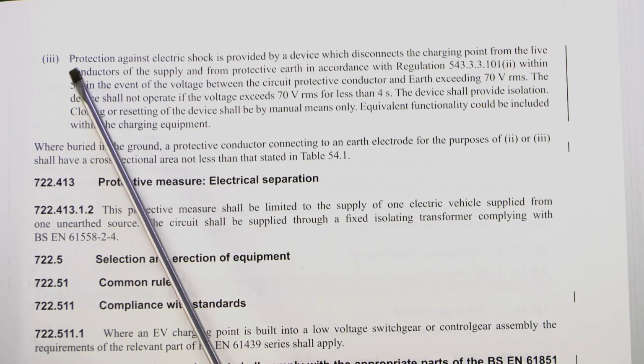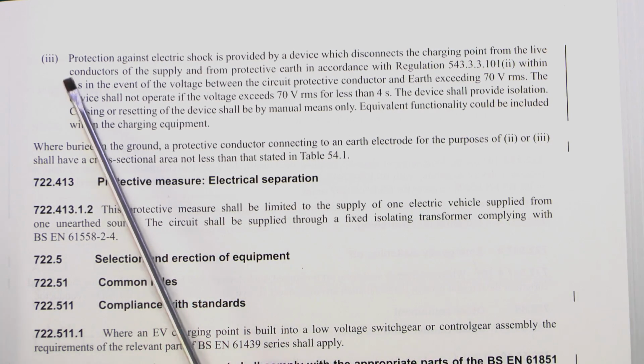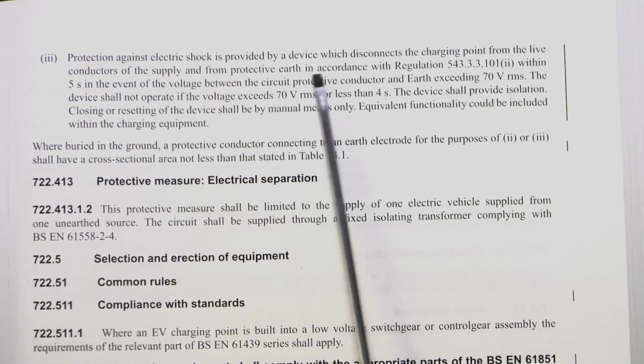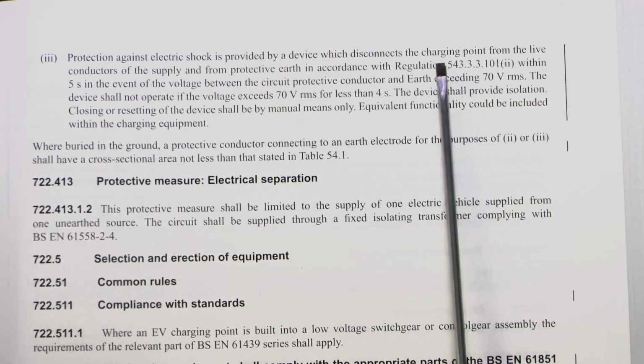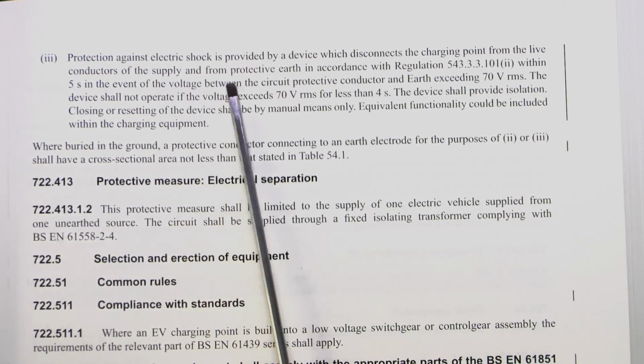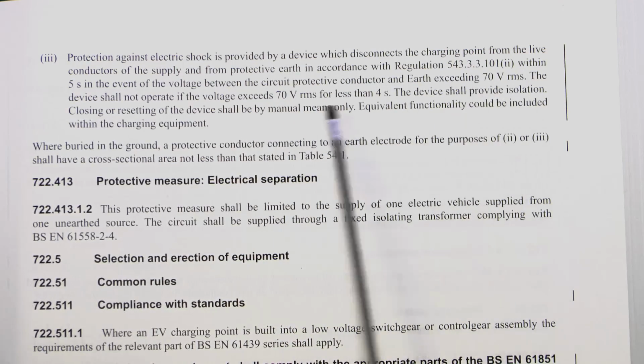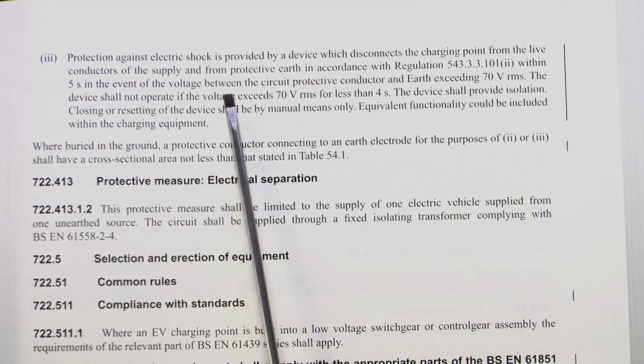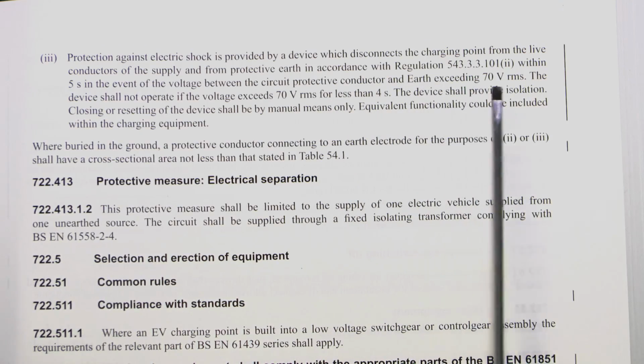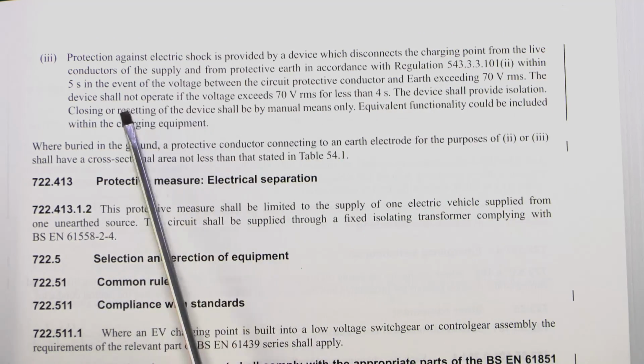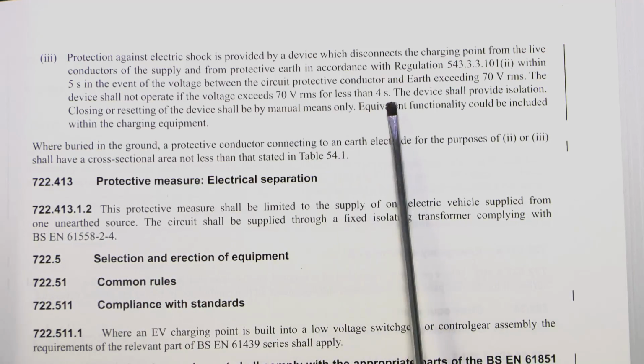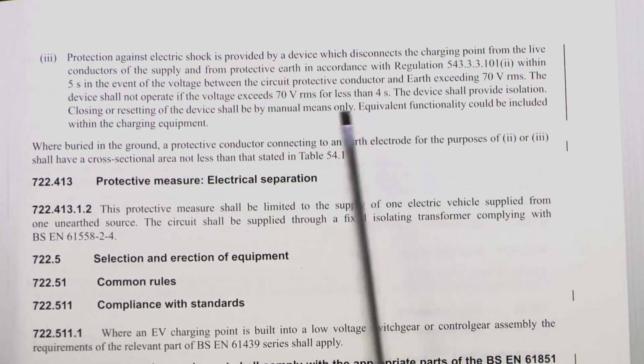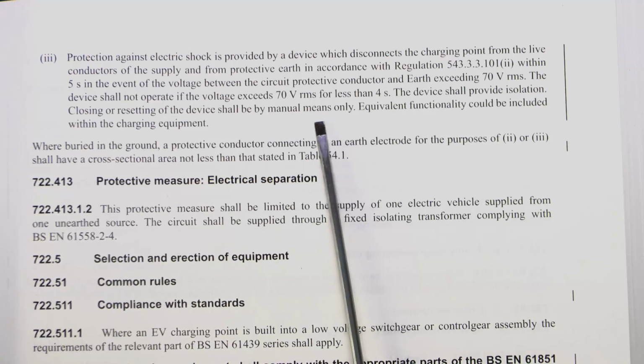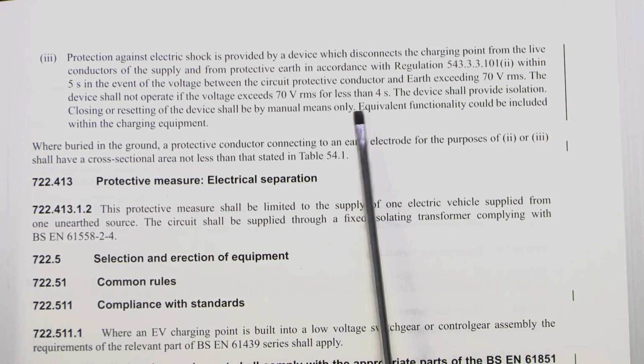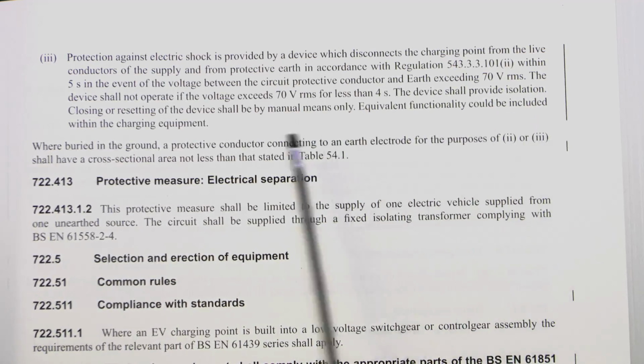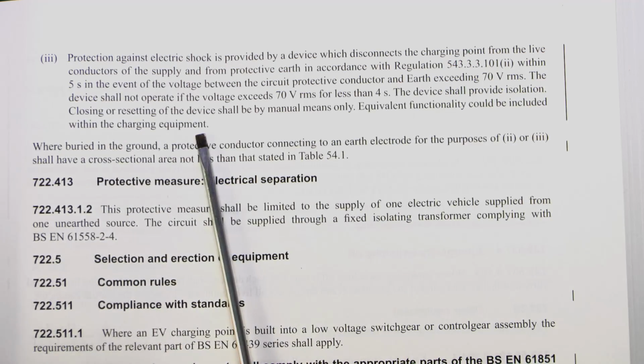So basically it comes down to the third item here, which is what you're going to be having to use. Protection against electric shock is provided by a device which disconnects the charging point from the live conductors of the supply and from protective earth in accordance with the regulation within 5 seconds in the event the voltage between the circuit protection conductor and earth exceeds 70 volts. The device shall not operate if the voltage exceeds 70 volts for less than 4 seconds. The device should provide isolation, closing or resetting manual means only, and then the bit that's been added here, it starts there: equivalent functionality could be included within the charging equipment.